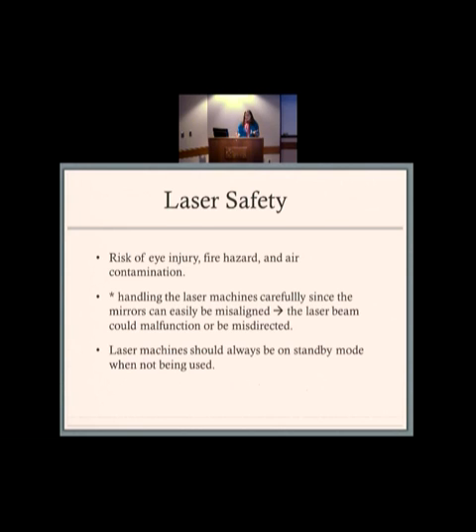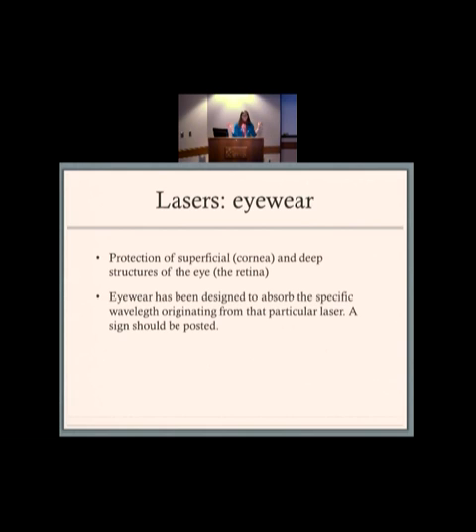This is something that I thought was interesting, which I would put a little star by. I need to be mindful of it too, but I don't know, do you guys handle the lasers at all? Okay, well, just in case you do, here's something to be mindful of. There are little mirrors inside the machines, and if those mirrors get broken or misaligned, you get freaky laser beams. So it could do a lot of damage. Laser machines should always be on standby mode when not in use. So if you walk into a room where the laser guy is talking to the circulator about what they did on Friday night, and you come in like, oh, that's still on, turn it off. Not that that's ever happened here, I was just making that up.